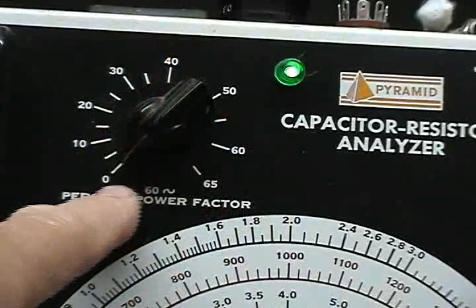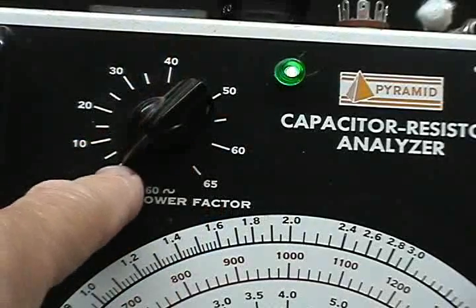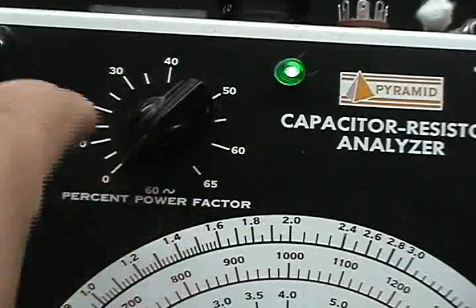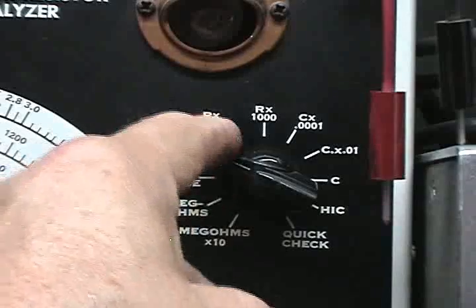Power factor loss, so on electrolytics your power factor should always be really down here. Anything in that 10 or 20 percent is a loss. This is registering power factor in loss, and of course you got the ranges for the leakage and capacity.